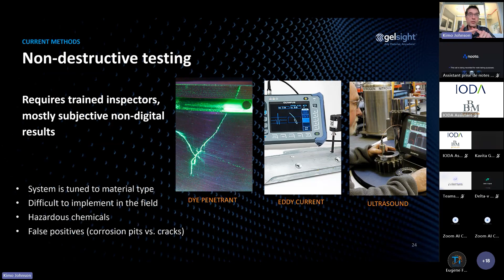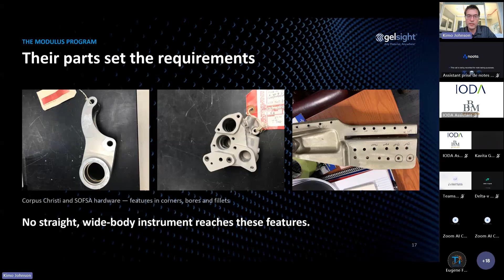Once we saw the variety of components being inspected daily, it was obvious there's no one-size-fits-all solution, especially since visual inspection drives a lot of these decisions. One story involved a matte black helicopter blade that had passed visual inspection. When the inspector told me where they typically find cracks, I put the GelSight probe on it and got a scan showing a crack that had escaped visual inspection. They confirmed it was there after I found it, and said they were fortunate we'd been on site, because this would have gone on the helicopter and potentially failed in flight. It shows the challenges of visual inspection.